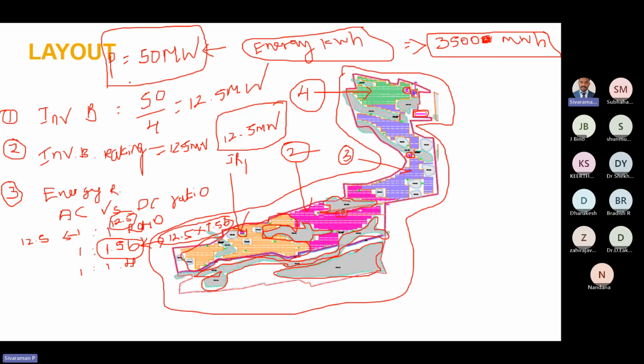One is power. How are we considering it? 12.5 multiplied by 4. So we have 4 inverter rooms, that is this 4, and the inverter block capacity is 12.5. So multiplying 12.5 with 4, we will get 50 megawatt. So we are able to meet the power requirement.